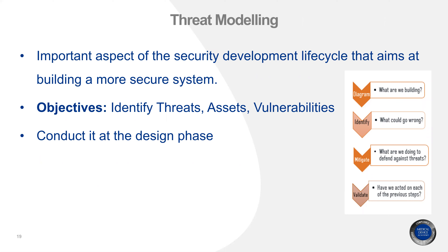Threat modeling is an important aspect of the security development lifecycle that aims at building a more secure system. It enables the organization to build security requirements into the system or device and does not address cybersecurity as an afterthought — therefore it is conducted at the design phase. Threat modeling aims at identifying assets, analyzing threats and vulnerabilities, and mitigating them. It can be performed in four steps: diagram (what are we building), identify threats (what could go wrong), mitigate (what are we doing to defend against threats), and validate (how have we acted on each of those steps).